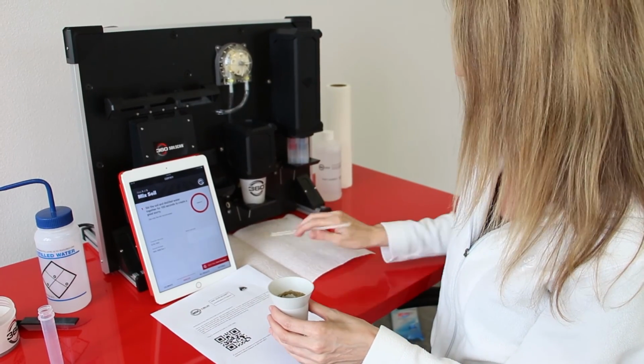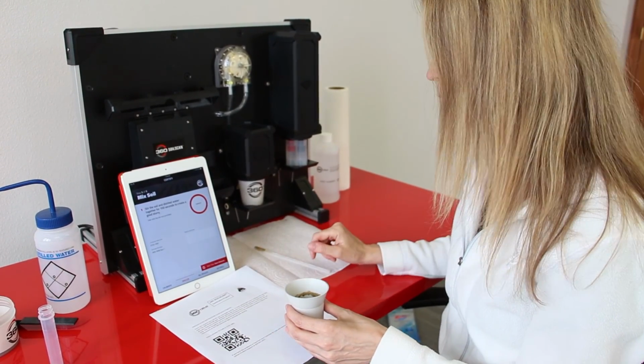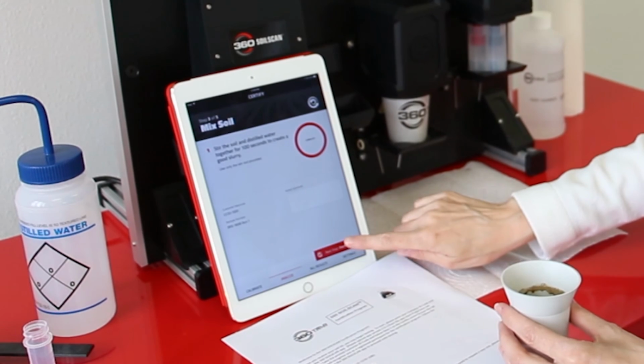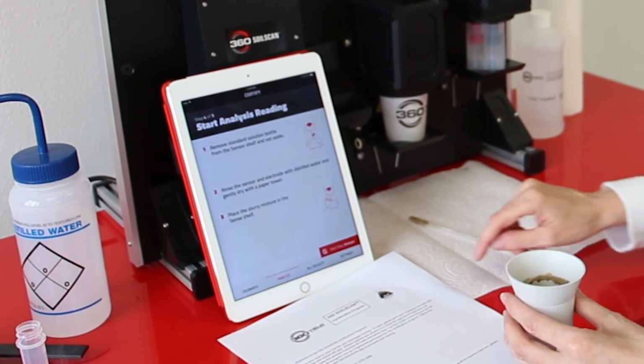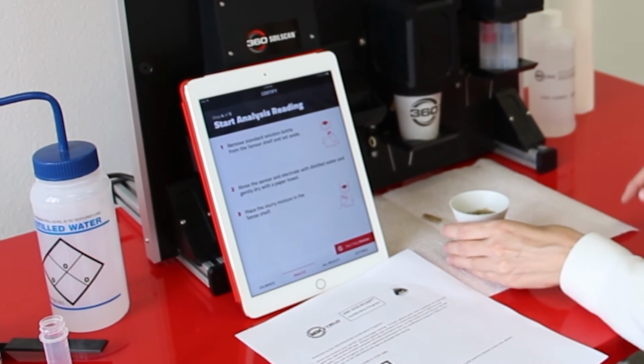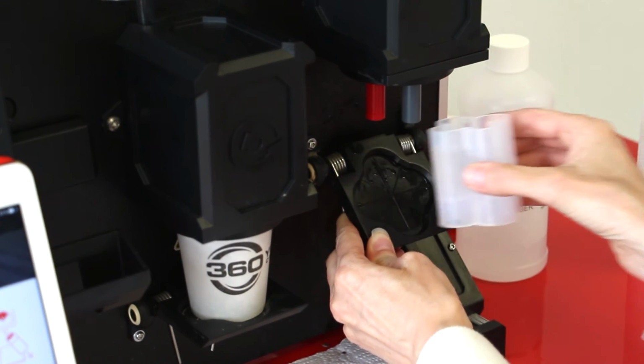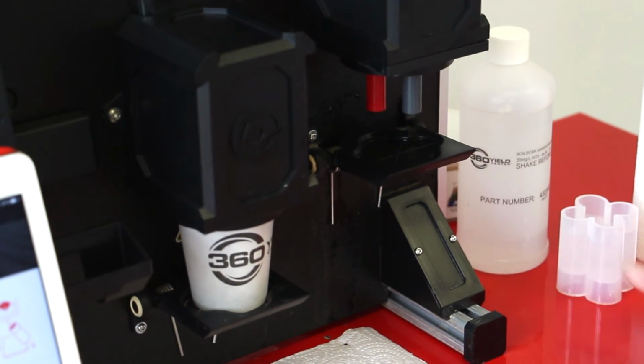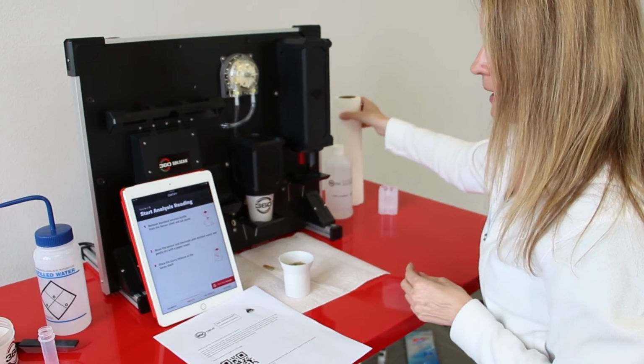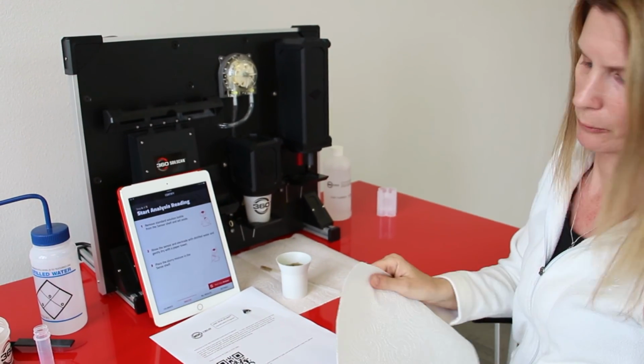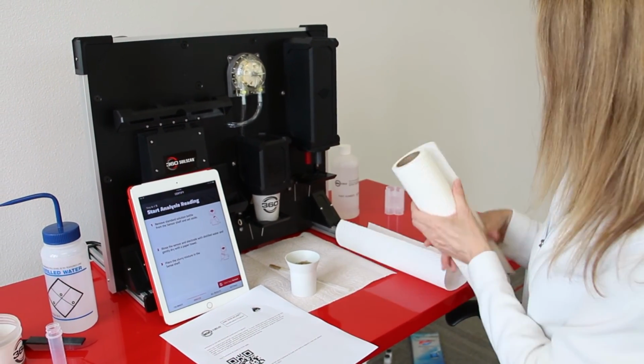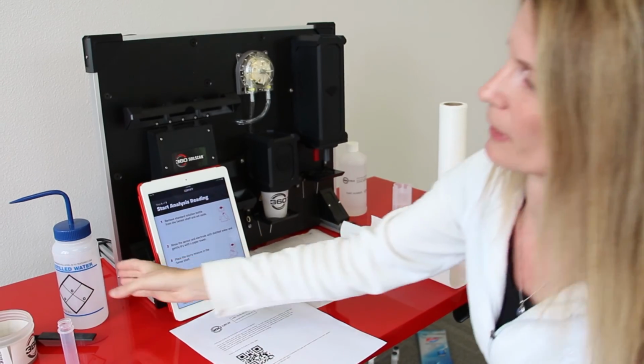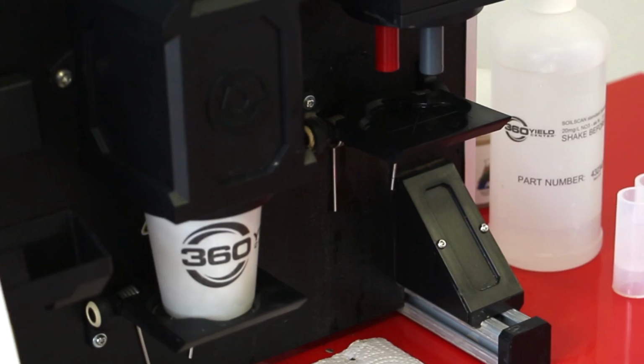Okay, and as you can see from the app, we've completed the stirring process. So then we're going to hit next step, start analysis down below. And we're going to follow the steps here. Step 1 says to remove the standard solution bottle from the sensor shelf and set it aside. And then we're going to rinse the sensor and the electrode with distilled water and wipe it down with a paper towel. So I've got some distilled water right here.